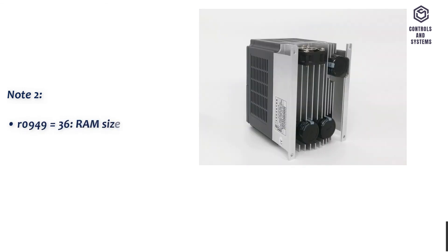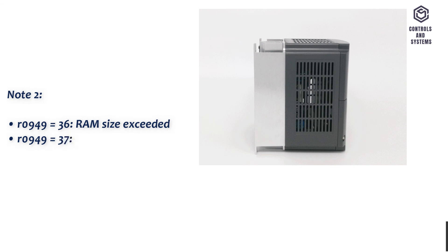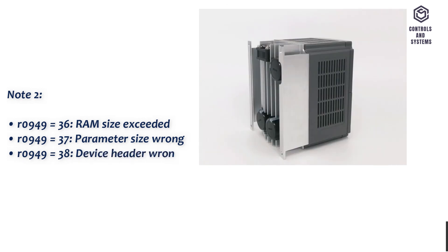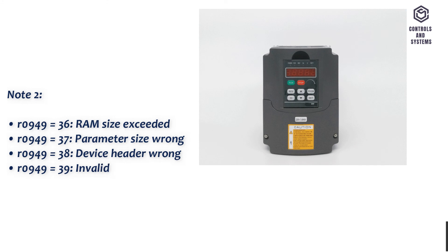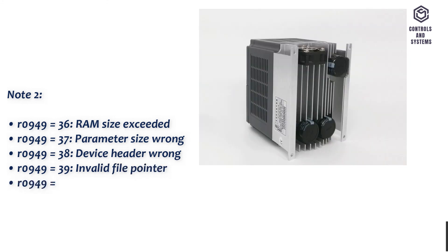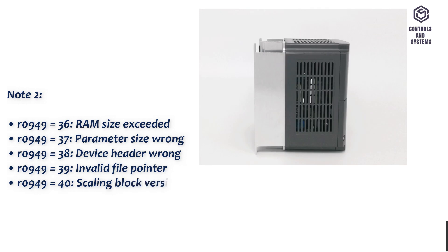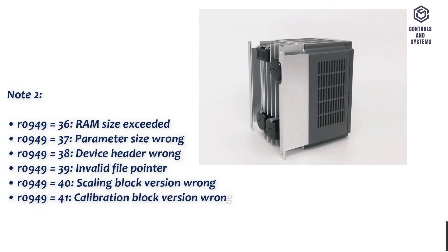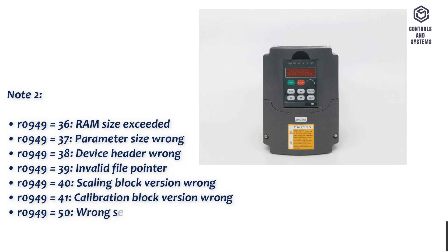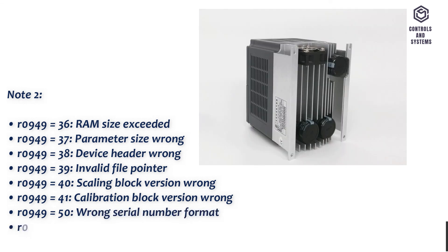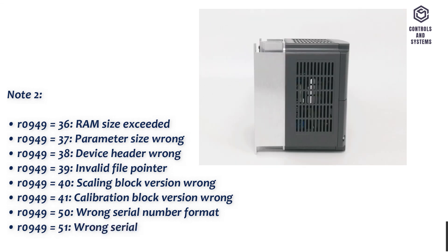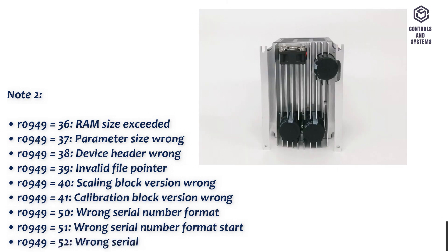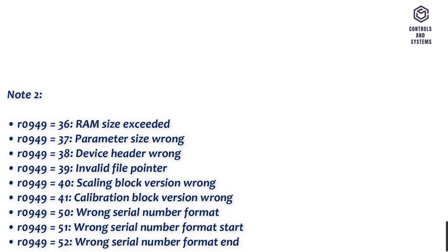Note 2: R0949 equals 36: RAM size exceeded. R0949 equals 37: parameter size wrong. R0949 equals 38: device header wrong. R0949 equals 39: invalid file pointer. R0949 equals 40: scaling block version wrong. R0949 equals 41: calibration block version wrong. R0949 equals 50: wrong serial number format. R0949 equals 51: wrong serial number format start. R0949 equals 52: wrong serial number format end.